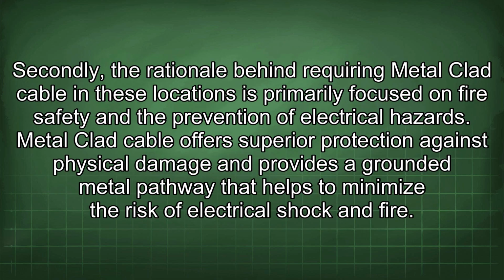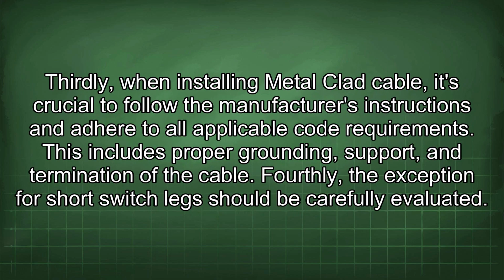Secondly, the rationale behind requiring metal-clad cable in these locations is primarily focused on fire safety and the prevention of electrical hazards. Metal-clad cable offers superior protection against physical damage and provides a grounded metal pathway that helps to minimize the risk of electrical shock and fire. Thirdly, when installing metal-clad cable, it's crucial to follow the manufacturer's instructions and adhere to all applicable code requirements. This includes proper grounding, support, and termination of the cable.